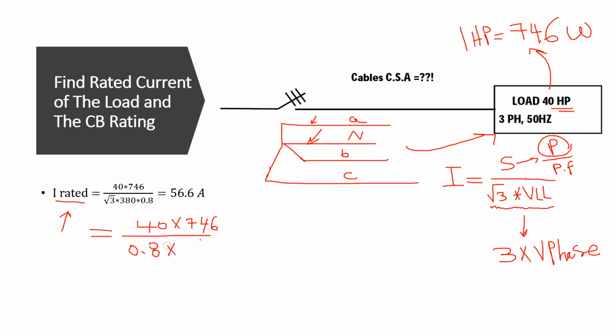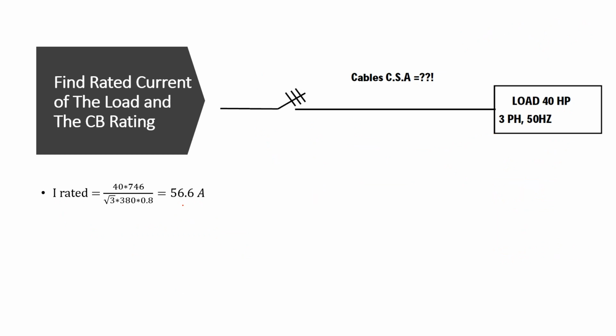This part representing the apparent power S is divided by root 3 multiplied by the line to line voltage. In my own country, for example, it will be 380 volt. It is different from one country to another. So all of this will give us a final rated current of 56.6 ampere. So this is the rated current absorbed by our load. I rated is equal to 56.6 ampere. This is the first step.